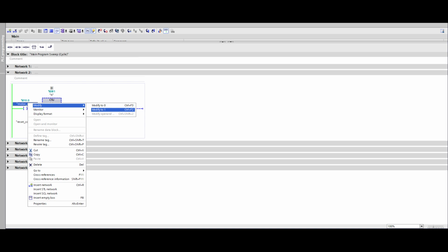This happens only once at each scan cycle. A scan cycle is the PLC loop: it reads all the inputs, runs your program, and then updates the outputs. The important point here is that I0.0, which is the input, stays locked for the whole cycle.